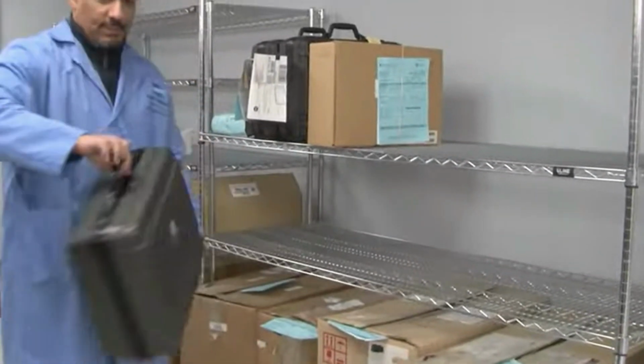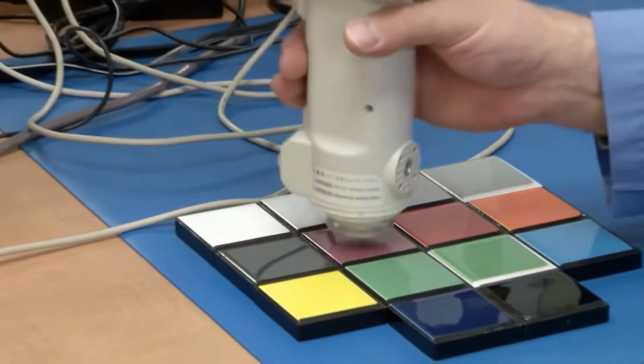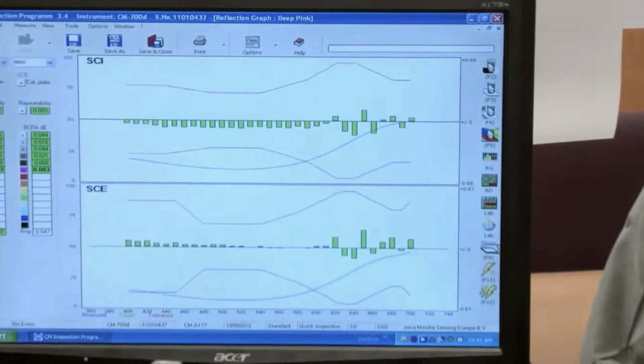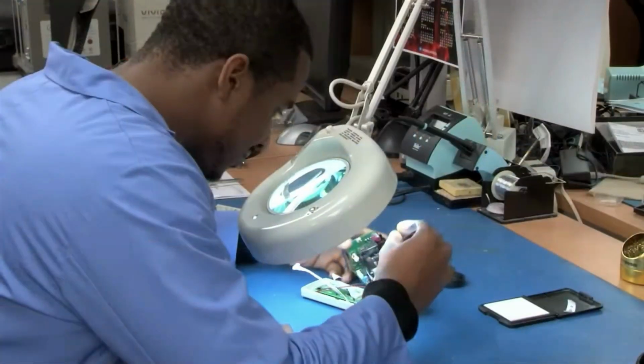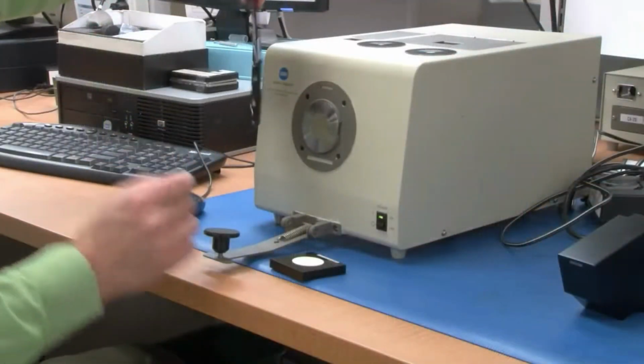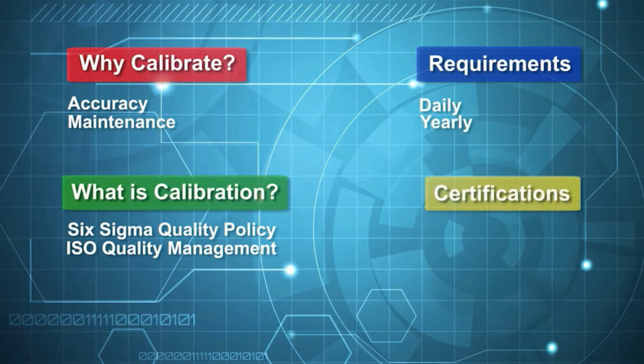You can send your instrument to our facility or hire a skilled technician to calibrate on site. The customer should send both the white tile and their instrument in for service annually. By sending it here, you have traceability all the way back to NIST through Japan. And that's important for a lot of customers. So we have the capabilities to do any type of repair and any necessary adjustments, and finally calibration. Certifications received from annual calibration of your color or light measurement instrument are ISO and NIST.